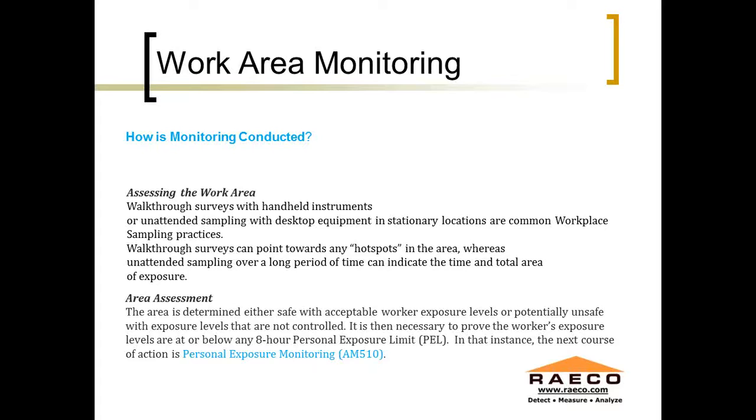Right here, work area monitoring. This is just talking a little bit about assessing the work area. You know, different ways to do it. You can walk through with a handheld instrument, which is typically what you want to do to identify hotspots.